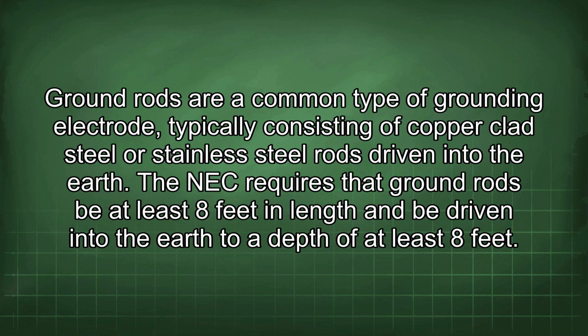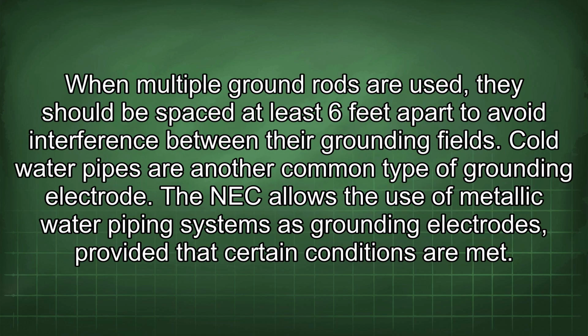Ground rods are a common type of grounding electrode, typically consisting of copper-clad steel or stainless steel rods driven into the earth. The NEC requires that ground rods be at least 8 feet in length and be driven into the earth to a depth of at least 8 feet. When multiple ground rods are used, they should be spaced at least 6 feet apart to avoid interference between the grounding fields. Cold water pipes are another common type of grounding electrode.